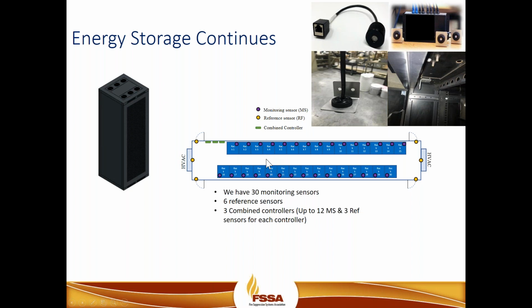So if we were looking to design a system for off-gas monitoring in this type of system, we would want to place a sensor in each individual rack and be able to identify the off-gas event as it occurs inside of the rack. Now, of course, if this is a hot aisle configuration and the racks are sharing the hot aisle, we could look for economies of scale and introduce a methodology where we place one sensor between two racks. However, in that type of configuration, you would be introducing dilution factors, and you would be less likely to respond to the event in early enough time, or you may not be able to respond to the event at all prior to thermal runaway. So for this particular example, we have 30 monitoring sensors, 6 reference sensors that you see here as reference detection, and also 3 controllers reporting to the BMS system and the FACU.